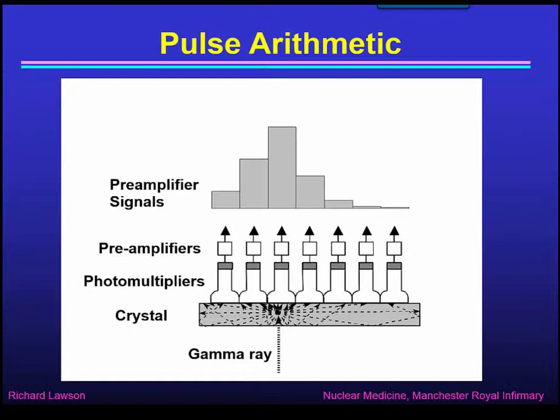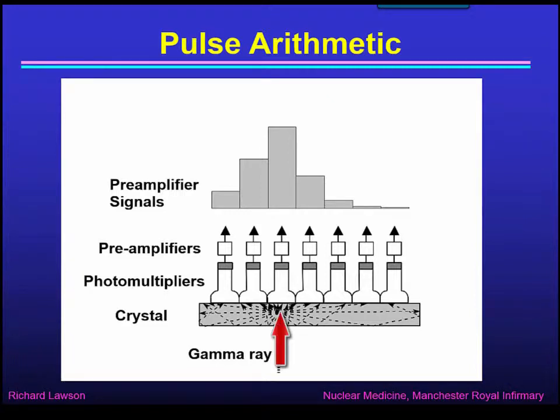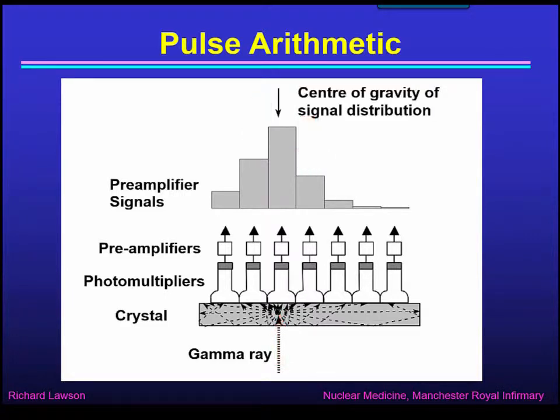The amount of light collected by each photomultiplier depends on how close it is to the scintillation point, so the photomultiplier at its closest produces the biggest amount of light. We can use that as a rough idea of where the gamma-ray interacted, but we can do better by looking at the signals on either side. In this case the gamma-ray interacted slightly to the left of centre, so we can use the centre of gravity of the signal distribution as our best estimate of the position where the gamma-ray interacted.